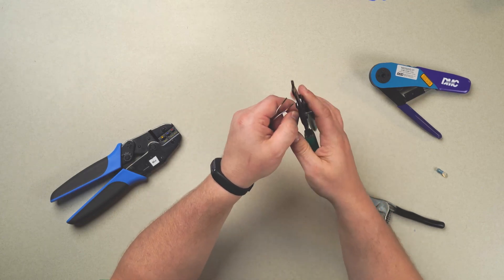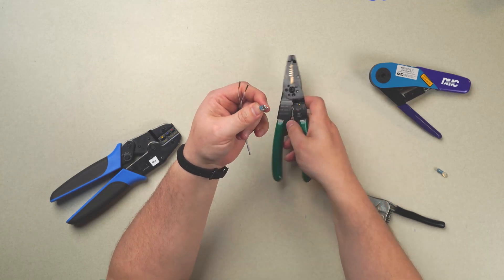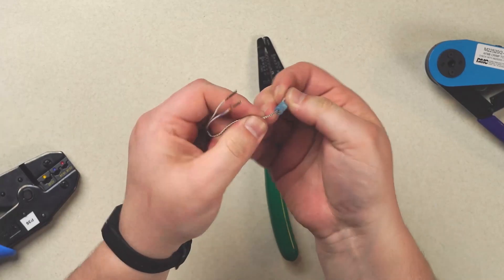And we crimp right in the center, center mass. The reason this is not desirable is, as you can see, it really tears up the ring terminal and it doesn't always give us the most firm fit.